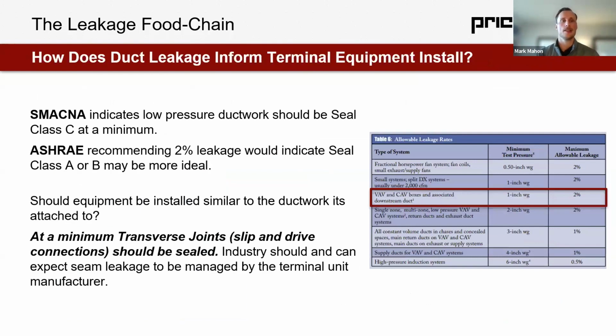My main takeaway would be, if we need seal class C at a minimum, those transverse joints, those slip and drives, all those extra accessories should really get sealed in the field as well. The actual seams of the terminal, in my opinion, the industry should and can expect seam leakage to be managed by the terminal unit manufacturer, but we do not seal externally slip and drives. Unless it's required, we can do it. We often do for different projects. It's an option from Price, but the stock single duct, which many of you would use regularly on projects, does not have slip and drive sealed. The expectation is those would be sealed in the field.